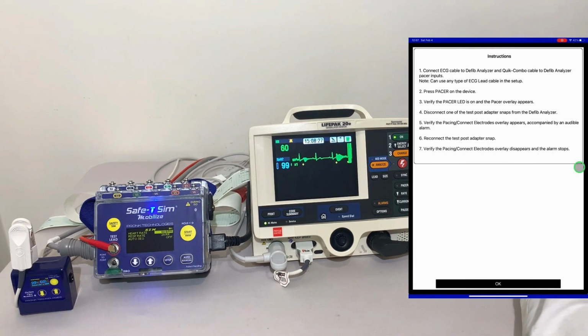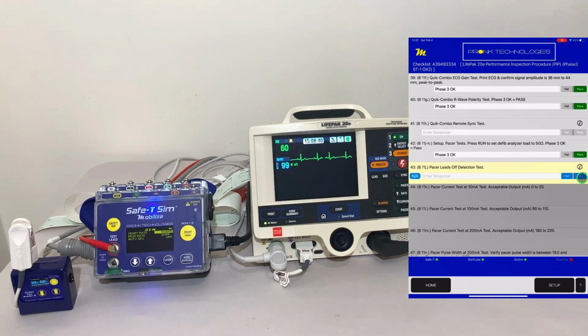We'll do that on the other lead to be sure. That's the second lead. And then the third lead also confirms that it detects pacer off. So it's important to make sure we do that. We're good with this. We've passed this test. Now we need to go ahead and do a current test.